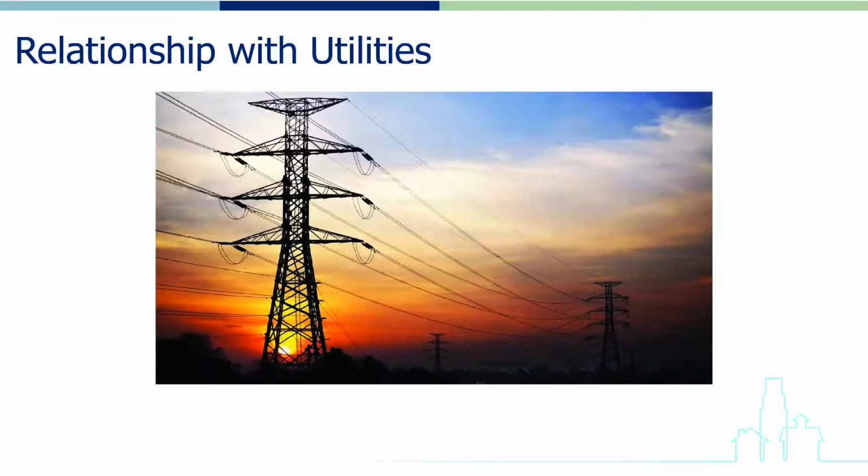A community microgrid has a complex but symbiotic relationship with the local utility that is mutually beneficial. The microgrid is a customer of the utility, using the utility's power supply when it is economically beneficial, and the microgrid can supply power and other energy services to the utility. Advanced microgrids also have black start capabilities, which means that generators can start up cold, supplying power without interruption so that customers are unaware of the shift between the grid and self-supply. The Institute of Electrical and Electronic Engineers has created standards and best practices for safe microgrid islanding, black start operations, and grid reconnection.